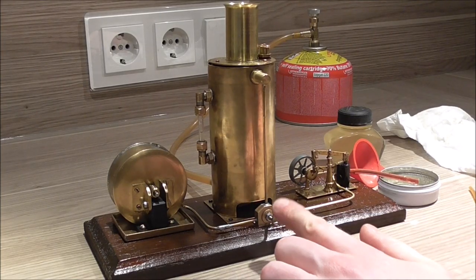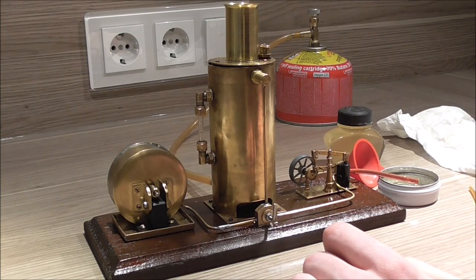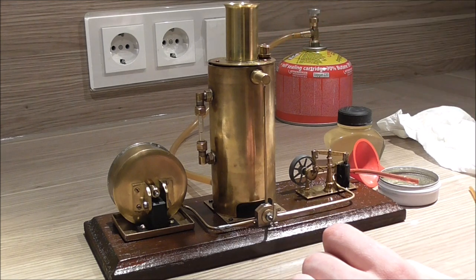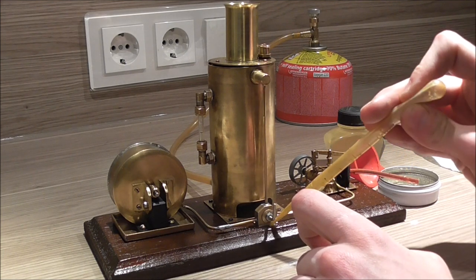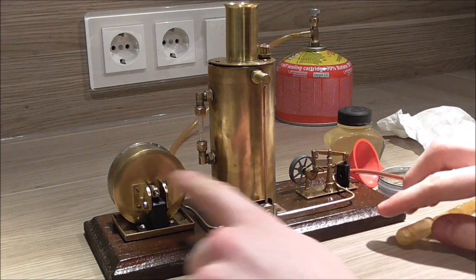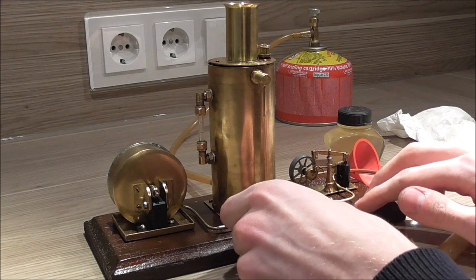Okay, I've shut the valve here off for some time. Then you can just about see the safety valve blowing a little bit of steam. And I think that's all we can get. You can see the valve has now started to leak with the rising pressure.